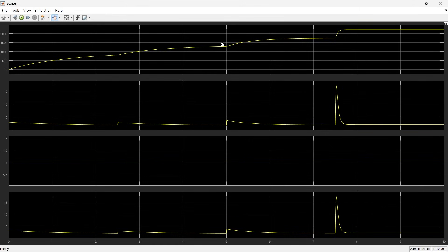Now you can see that the speed is increasing gradually. After 2.5 seconds the first resistance is cut off from the circuit and speed starts increasing again. After another 2.5 seconds another resistance is removed and speed rises further. It stabilizes briefly each time. After 7.5 seconds the last resistance is removed and speed jumps up to almost over 2000 RPM.